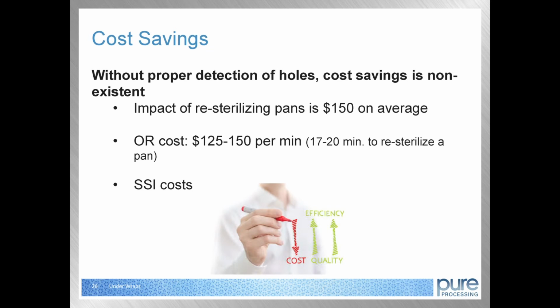And when you flash it, most of the time orthopedic pans have 4 different levels, so you're only able to flash 2 at a time. You take that 17 minutes for 2 layers, and then that adds up to 4 layers, and you get where I'm coming from. All of those costs start to add up, and that totally gets rid of the cost efficiency and the cost savings. And then, of course, it puts the patient at a higher risk and a higher chance of an infection. And then you have decreased physician satisfaction, which is important, but it's not as important as making sure the patient is safe and gets out of there safe.